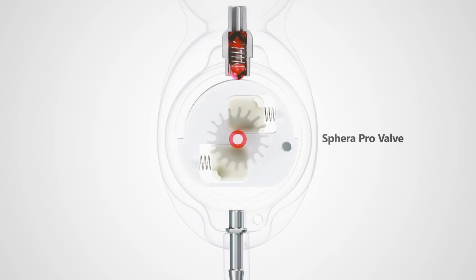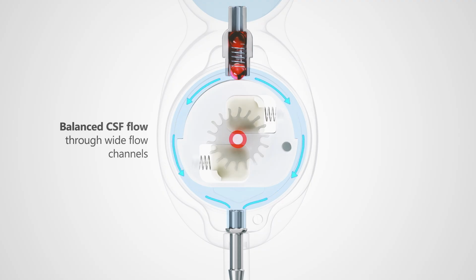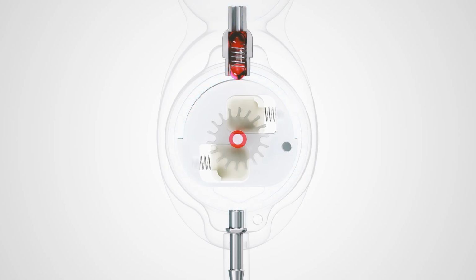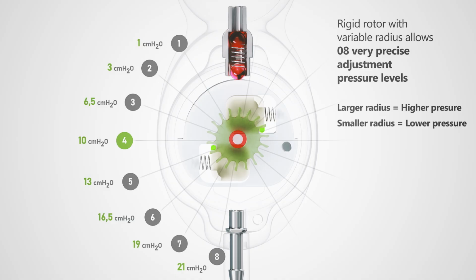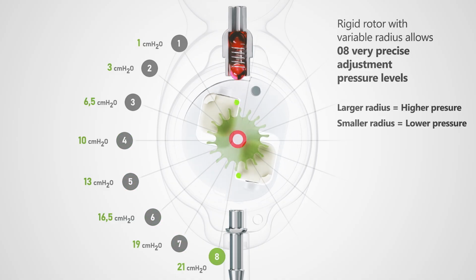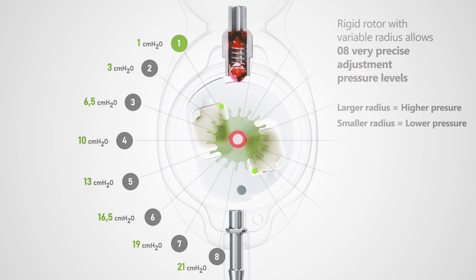When accessing the valve, the drained CSF presses the first ruby ball, opening the mechanism. The coil spring, pressed by the rotor, applies a CSF pressure resistance, keeping the drainage within the programmed pressure range. CSF flows around the rotor through wide flow channels. During pressure adjustment, the two locks are magnetically released by the programming device, allowing the variable radius rotor to move. When the rotor rotates counterclockwise, the valve pressure increases. When the rotor rotates clockwise, the valve pressure decreases.